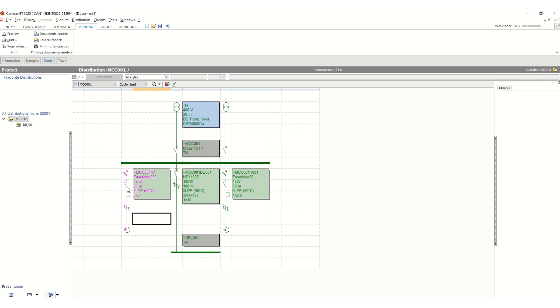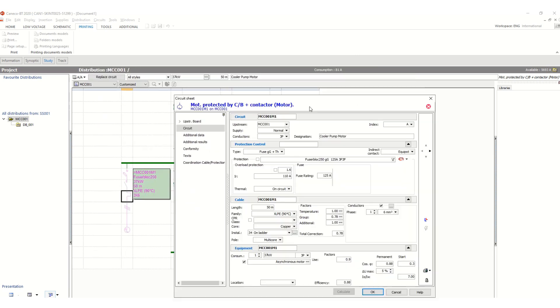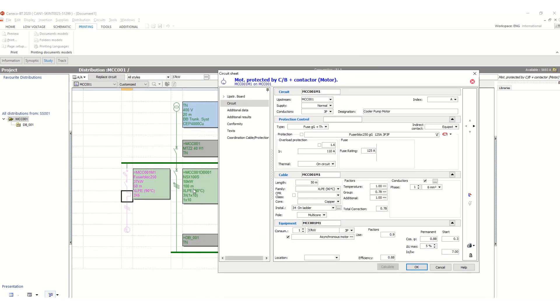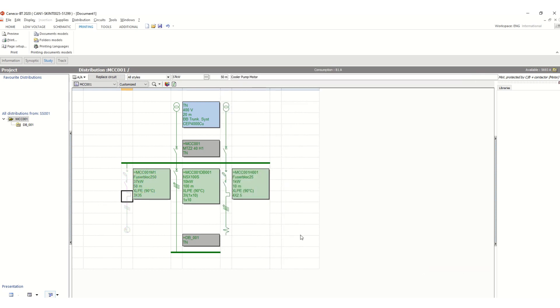The color changed because there is a violation. You can check from the colors whether it is acceptable — if it is in green then it's OK, but if there is an error or it is not sufficient, the color will change. Let's go back to 35 square mm and calculate again. Click OK — now you see the color has changed back to its original. Like this, you can calculate low voltage cable sizing with the help of CanecoBT software.